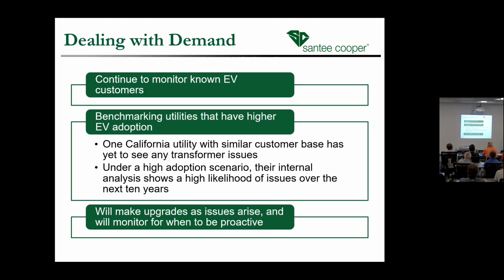So not to say we shouldn't do anything, but also you don't have to run back to your management and say EVs are going to destroy the grid tomorrow or anything like that. But they did say that under a high adoption scenario, which they think is somewhat realistic, their internal analysis showed a high likelihood of issues over the next 10 years. I think they said - I'm trying to remember the exact numbers - about 15,000 of their 50,000 transformers were expected to be overloaded by 2030 if they hit this high adoption scenario. So even if they don't hit the high adoption scenario, even if you're talking 3,000 or 5,000 transformers, 10% of your transformers by 2030, that's still pretty significant. So they're going to have to do something to combat that.